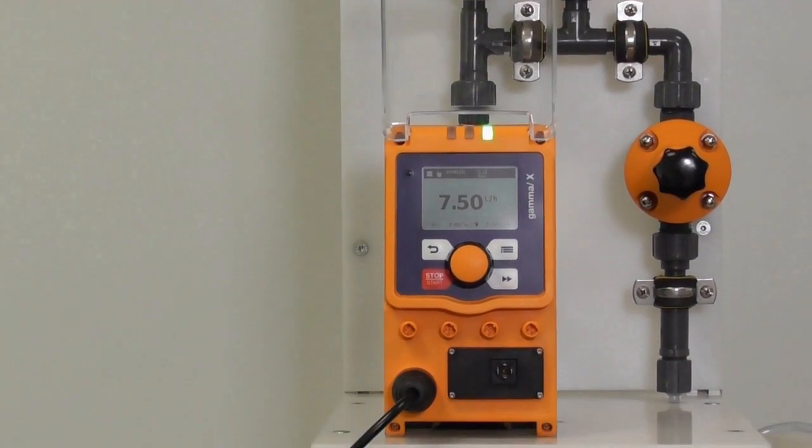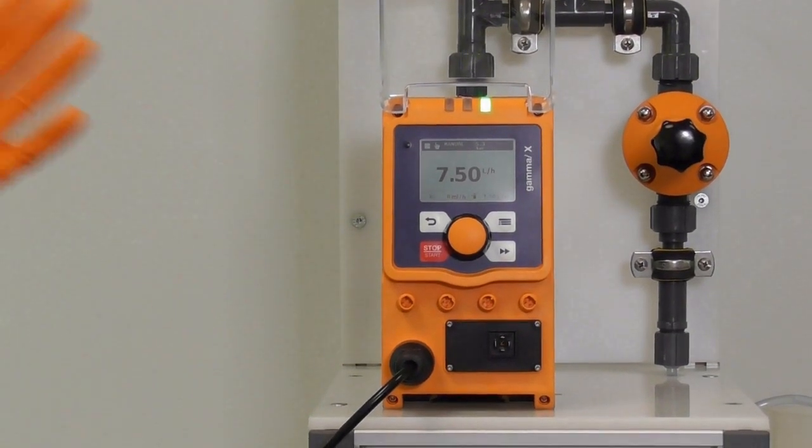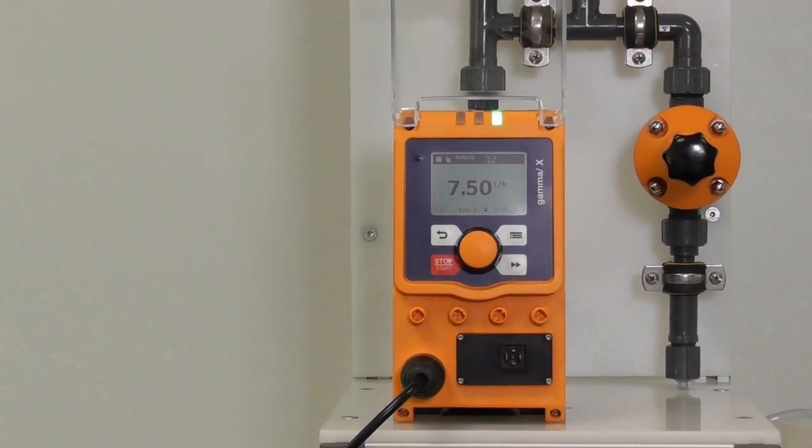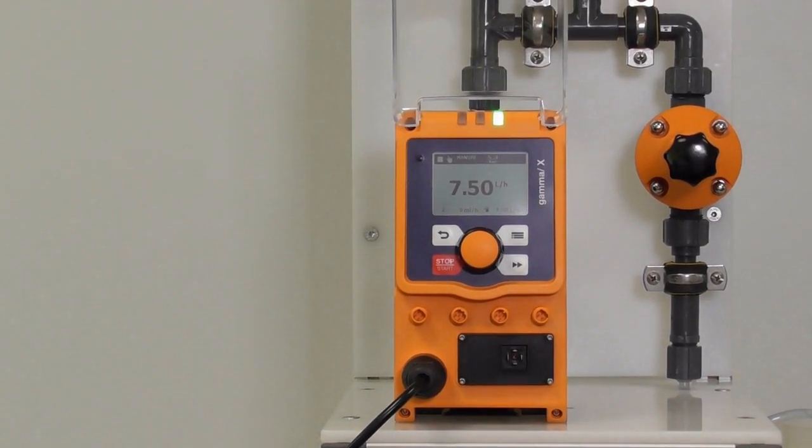Usually a calibration is not necessary when you handle liquids close to water. The pump is already pre-calibrated, but we strongly recommend a calibration when you handle viscous media or when you have a degassing dosing head like a PVT7 or a NPB9.